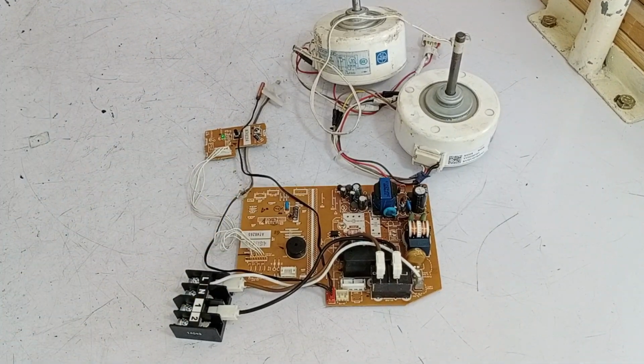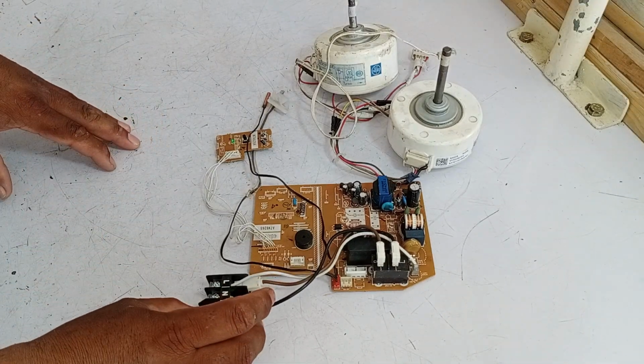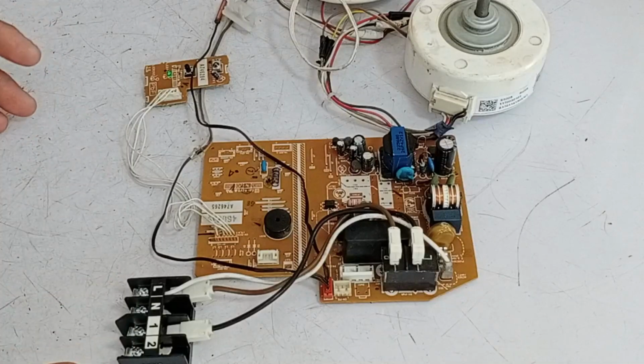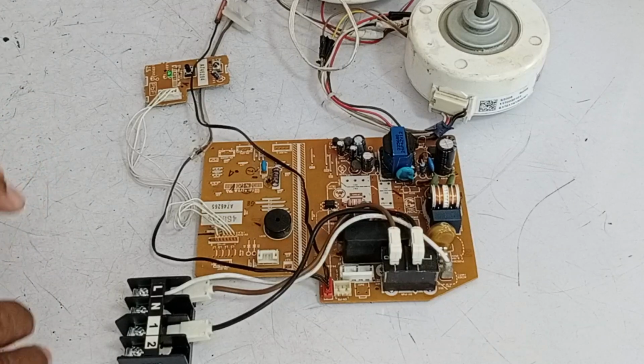However, we have the indoor unit, which can also have faults that cause issues. One unique aspect of Panasonic units is that they don't have error codes. Even if a sensor, motor, or any other component fails, the unit may just start tripping without indicating a specific error code. This makes it challenging to identify whether the problem is in the sensor, motor, room sensor, or elsewhere.